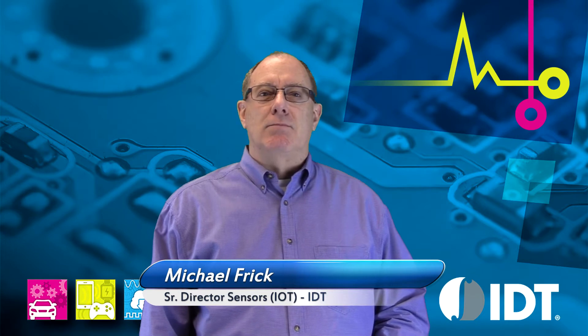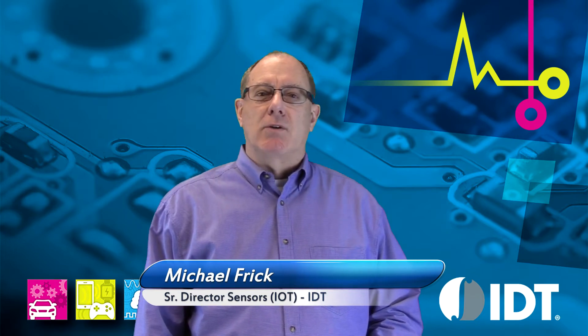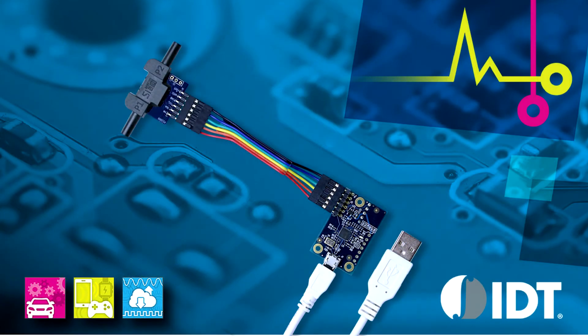This flow meter provides the ability to measure liquids and gas flow in both directions. The heart of the sensor is a patented hot wire anemometer made out of silicon carbide deposited on a porous silicon substrate. The porous silicon provides a structurally sound base for the sense element without a corresponding thermal loss. The construction makes the flow sensor very robust as there is no fragile membrane.